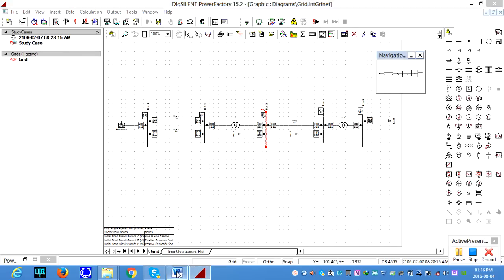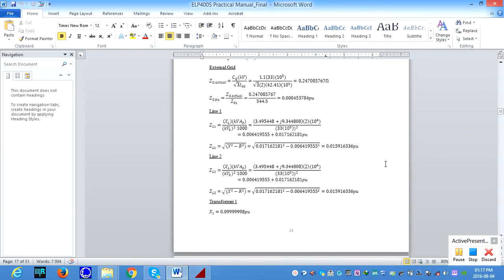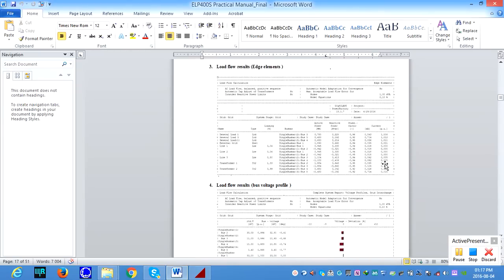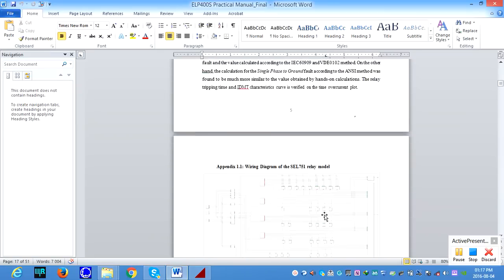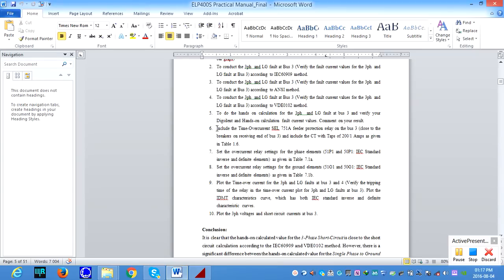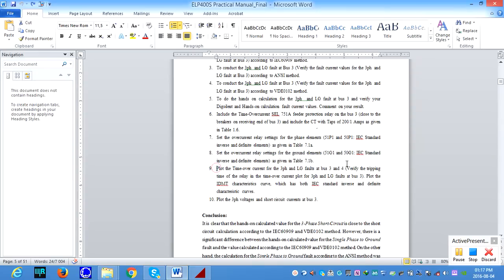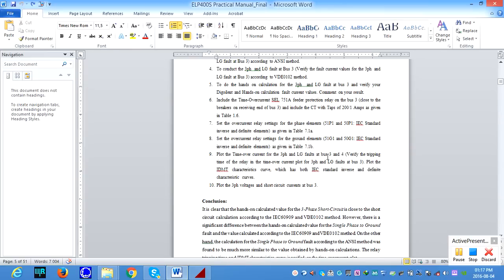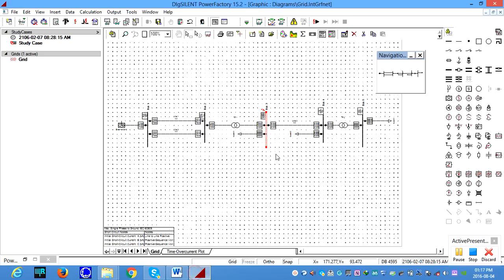next, go back to the manual. You need to validate the protection settings. Okay, to validate the protection settings, what is the next step? We included the time overcurrent plot, we did the settings for the phase elements, and we did the settings for the ground elements. We need to plot the time overcurrent plot. We did plot it, but we need to validate three-phase and line to ground faults at bus 3 and bus 4 and verify the tripping time in the overcurrent characteristics. I think in the time overcurrent plot, for the three-phase and ground fault at bus 3, we can quickly validate or verify.